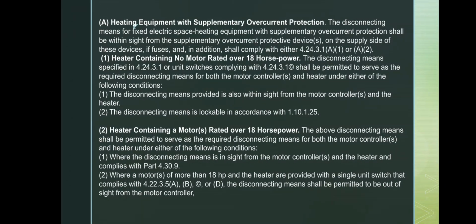Next slide explains the rules when heaters have supplementary overcurrent protection. First, heating equipment with supplementary overcurrent protection. The disconnecting means must be within sight of the supplementary protection on the supply side. If fuses are used, then it must meet either A1 or A2.